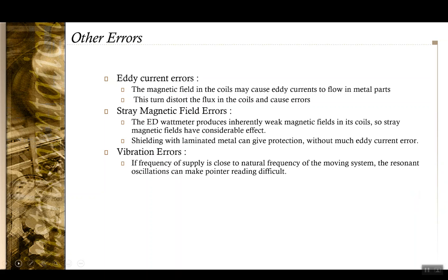Anyway, in this instrument you have a moving coil and a moving assembly that is itself a mechanical object, so it will have a mechanical natural frequency. If the supply frequency is close to that, there can be effects of vibration, which will make the reading difficult to read. The needle will vibrate a little, and so you cannot read it properly.